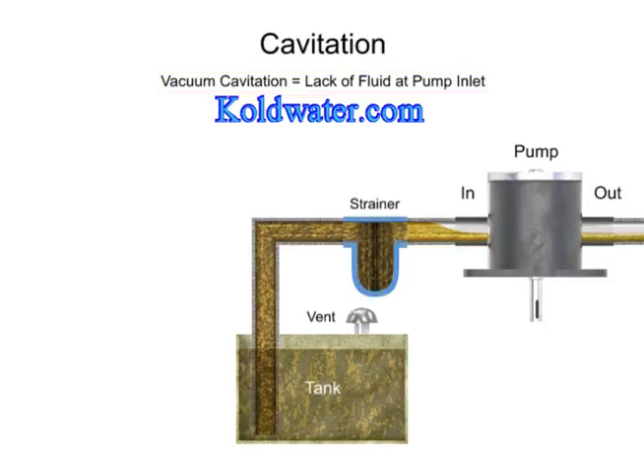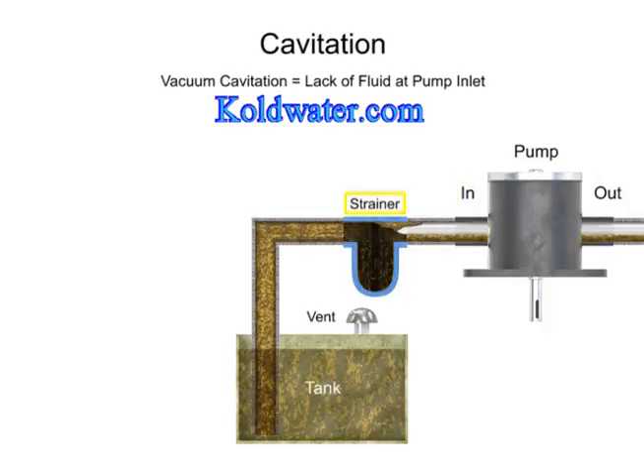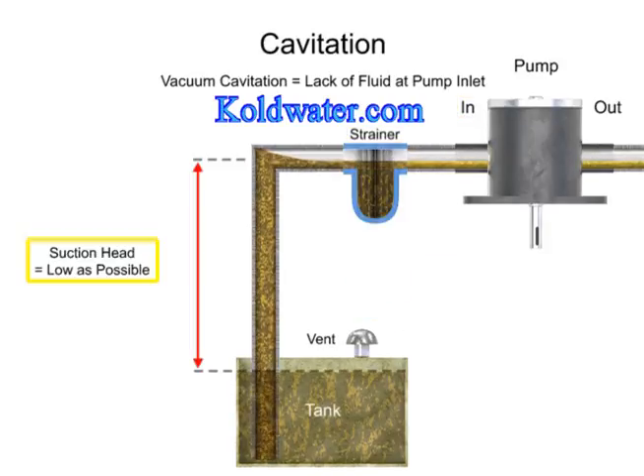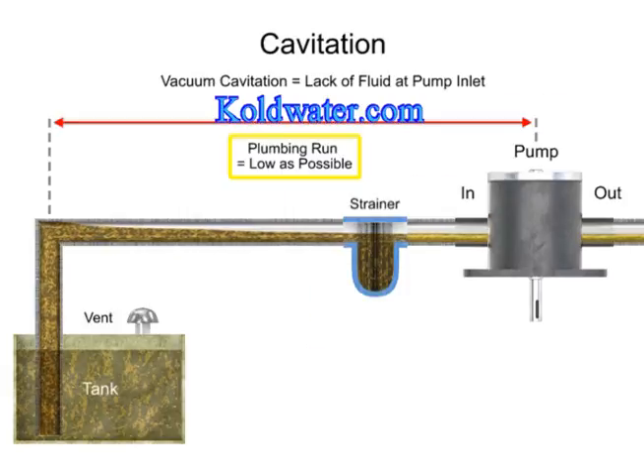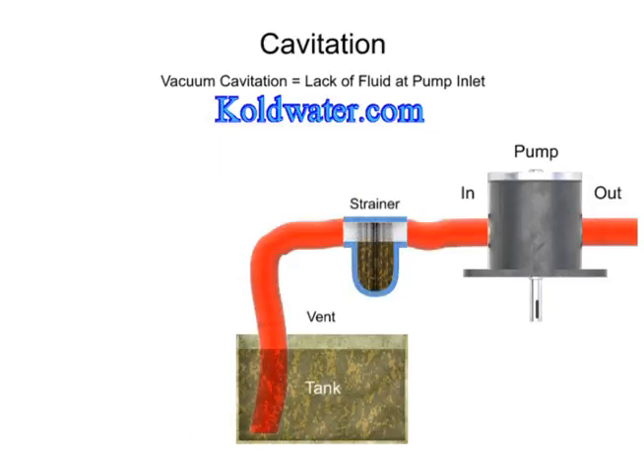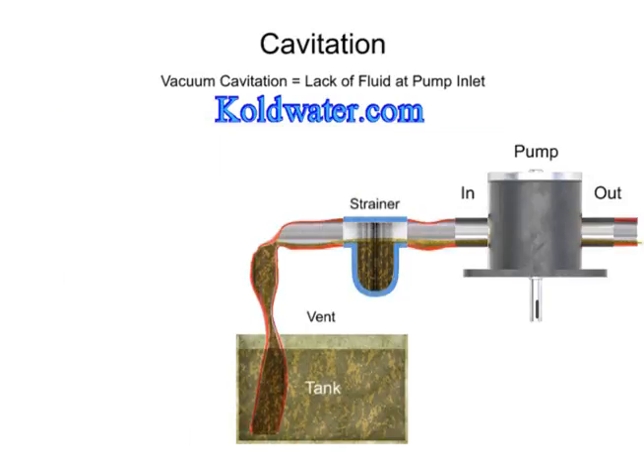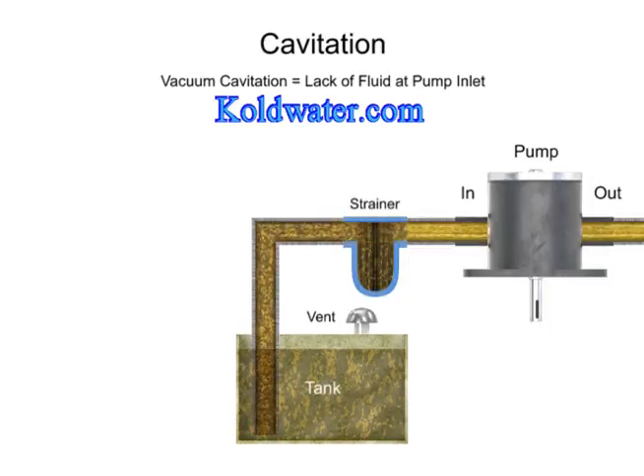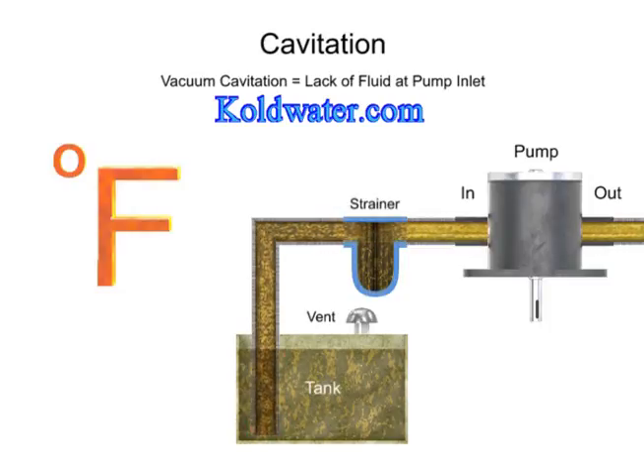The lack of sufficient fluid can be caused by a clogged inlet, a dirty strainer, too large a suction head, too long a plumbing run, restricted or collapsed plumbing hoses, or too viscous a fluid such as when the temperature drops and oil thickens.